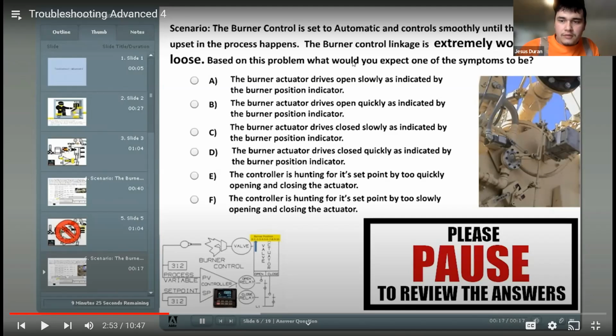It would be hunting for its set point, I think. All right, it pushes the fuel valve open from 0 to 7. 7's where you want to run. Now it calls for some more fuel. Well, the actuator starts moving, but the linkage doesn't move right away. Also, now it wants to cool down. Well, the actuator starts cooling it down, and all of a sudden it moves, and the slop is out of it now. Now it's pulling finally.